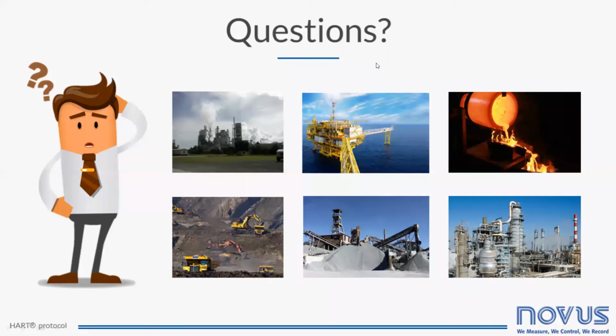I have another one here. Question: is HART one-way communication? No. HART has two-way communications, but it is half duplex. That is, it communicates one way at a time to send and to receive data through the digital signal. Okay, we have another one right here. What are the DD files in the HART? It is the file that defines the description of the HART device parameters. The communication diagnostic software interprets this DD file and determines how the device appears on the application and what are the parameters available.